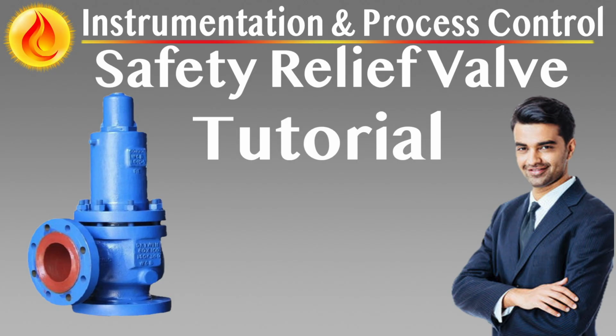Summary: pilot-operated relief valves provide a refined, high-performance solution where traditional spring-loaded valves fall short, particularly in high-capacity, tight margin, or high back pressure environments. Their superior sealing, accurate set pressure control, and compact footprint make them a compelling choice for clean, stable services. However, their reliability depends on meticulous design and maintenance of the pilot and sensing circuits, making them best suited to clean, well-controlled process conditions with minimal risk of contamination or blockage.